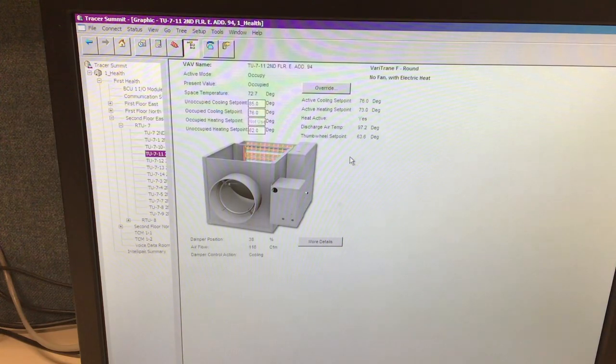If this goes above 110 degrees, I'm going to increase the minimum heating airflow to keep it from getting too hot coming out of the VAV, because there are high limit switches in there that we don't want to trip to manual reset, and nobody wants to have to go in the ceiling for something like that, mostly because it interrupts the tenant.